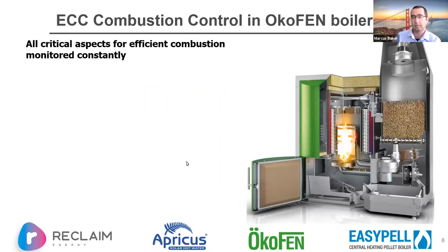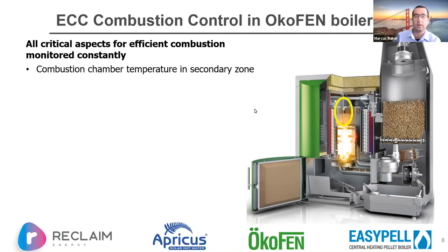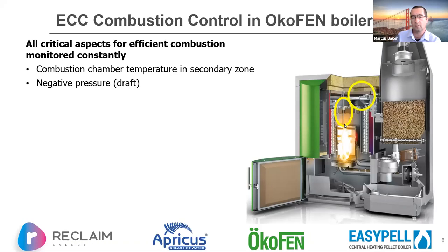In an Ökofen context there's what's called ECC — electronic combustion control — which is constantly monitored in real-time continuous commissioning. Temperature is monitored in the secondary zone to keep it in the optimum window. There's also negative pressure monitoring to determine how much air is moving through the system, which is a proxy for how much oxygen is available for combustion — getting that fuel-to-oxygen ratio just in the sweet spot.